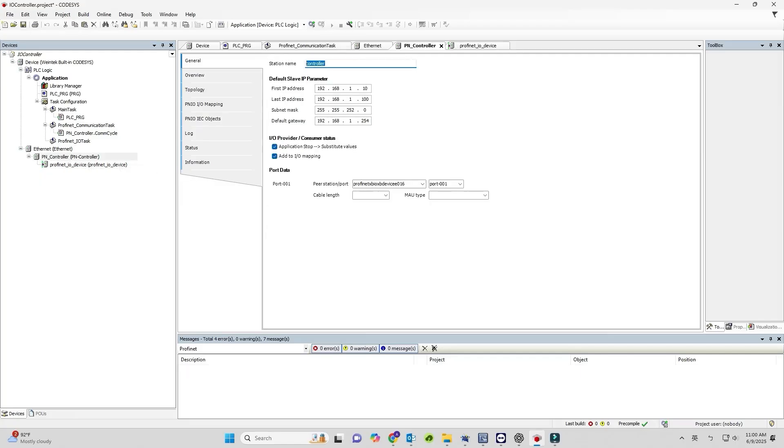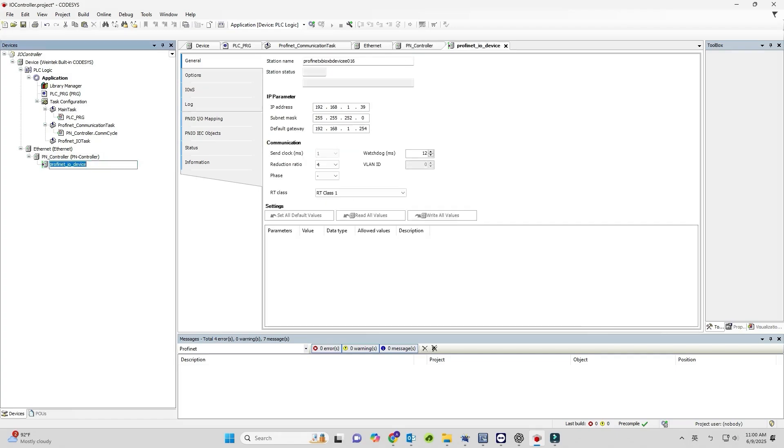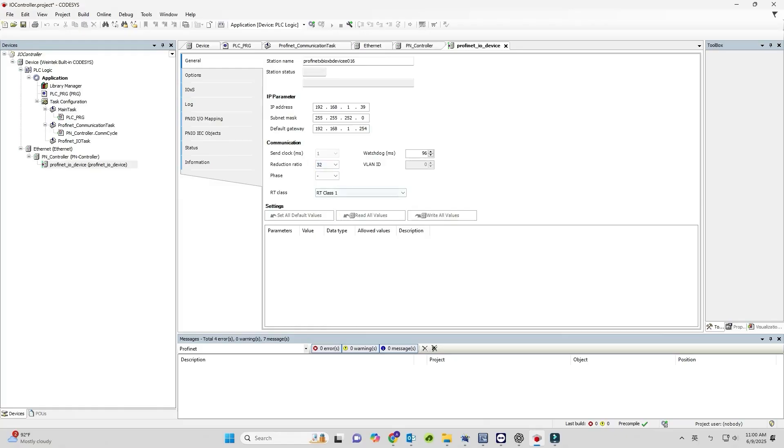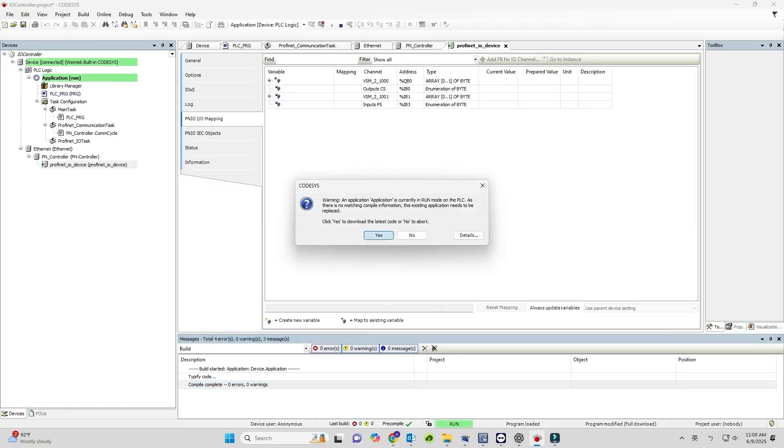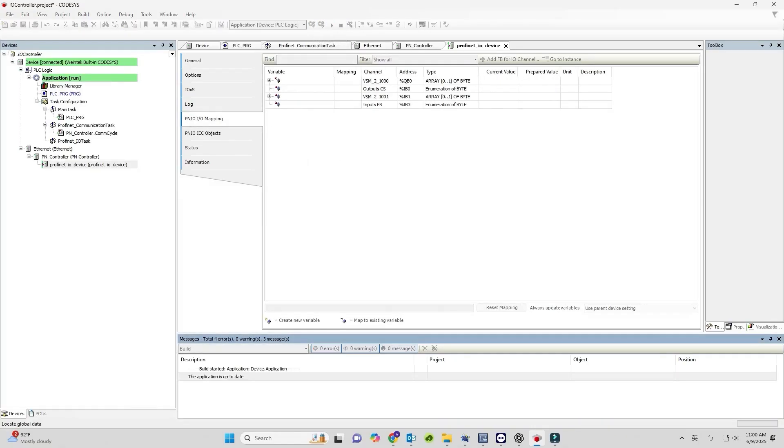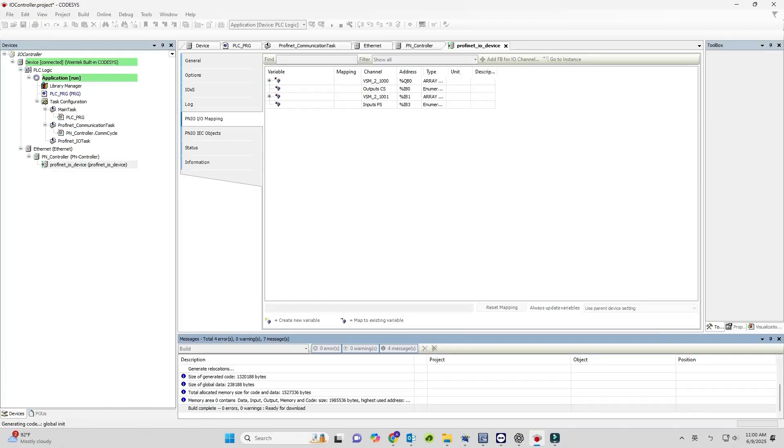Ensure the PN controller has a unique station name on the PROFINET network. Set the Reduction Ratio. For the first test, it's recommended to use the maximum value. When finished, download the project to the CODESYS PLC.